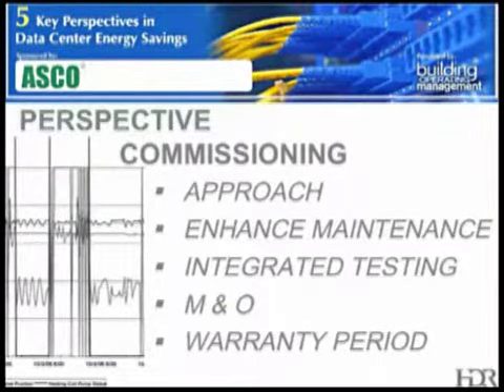And finally, as we move on into the warranty phase, this is often when the deferred tests are done. They could be seasonal tests done during the coldest or the hottest day of the year, or in the case of data centers, of course, we want the buildings fully loaded so that we can really see that our primary and secondary systems are operating correctly and our redundancy in our power systems is sufficient and working correctly. And one of the things we also do during this final phase is to evaluate what energy has been consumed, look at the energy model that was put together, look at system trend data, and then make those final set point adjustments on the systems.